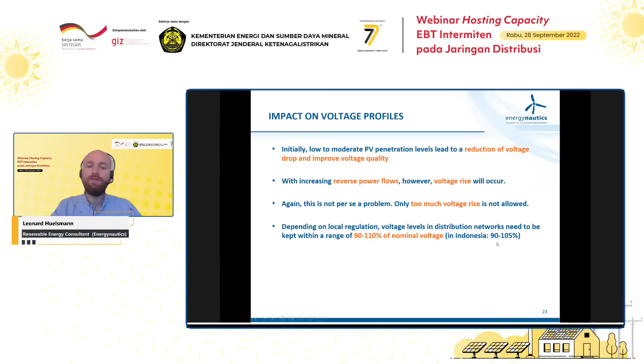In terms of voltage, also here, usually we have a voltage drop during peak demand. Initially, the distributed generation will reduce this voltage drop and actually improve voltage quality. However, with increasing PV penetration levels, at some point voltage rise will occur, and there are certain regulations on too much voltage rise. And in Indonesia, for example, voltage needs to be kept between 90 and 105% of nominal voltage.